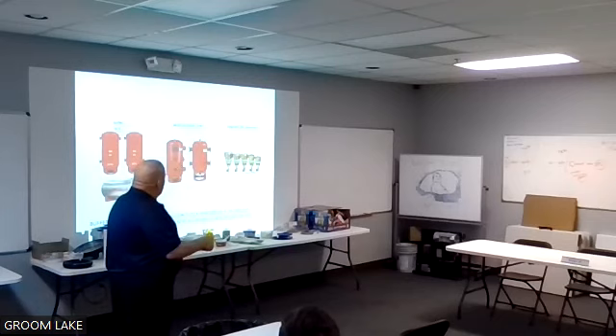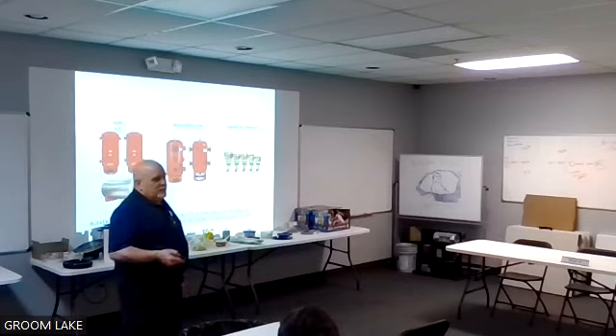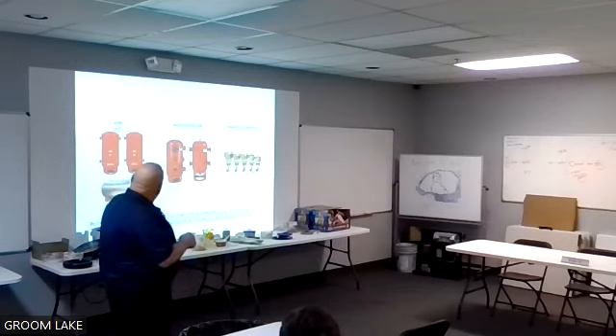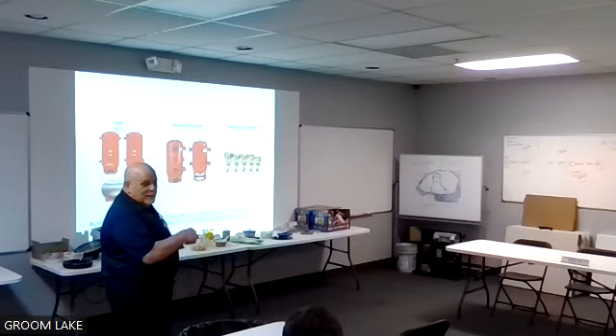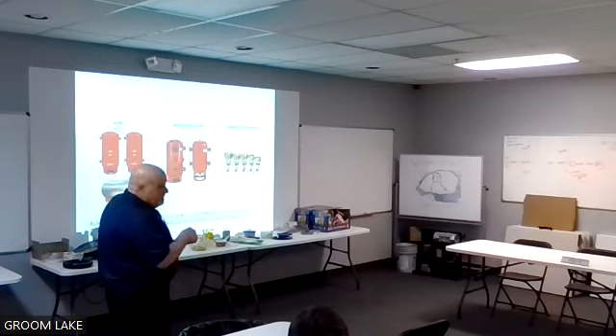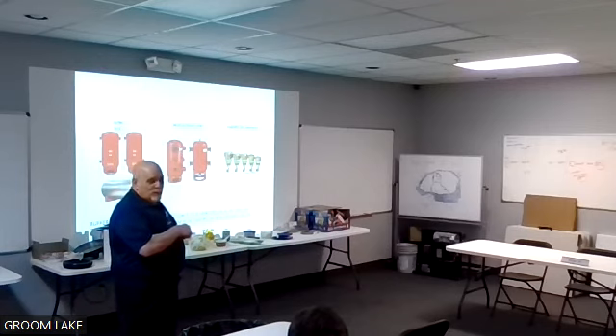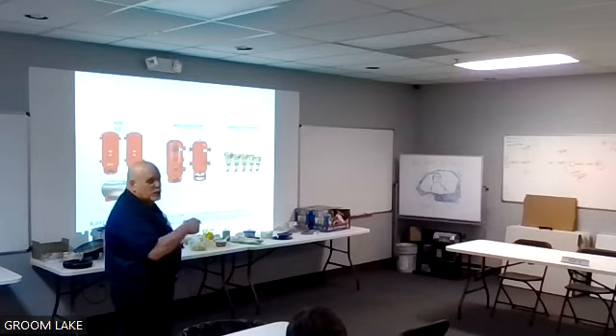The problem is if I decouple a small boiler loop here, that boiler might be running 100 GPM. So in 5 minutes, I need 500 gallons of water to go through that. My piping might only have 100 gallons of water. So I stick in a flow-through buffer tank of 400 gallons, or I put one of these in as my decoupler of 400 gallons. So if this system has no demand, once I start circulating the boiler, I have 400, 500 gallons of water I have to heat before it satisfies. I can keep that boiler or chiller on long enough so it doesn't go off on high head.